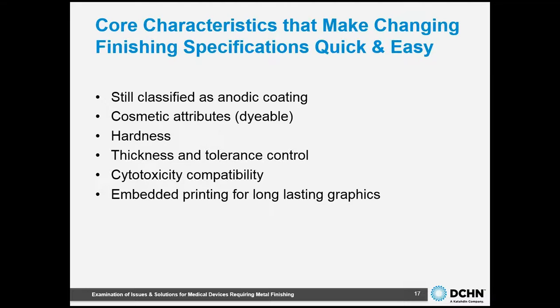So we discussed a lot about best practices solutions to this nagging problem medical device manufacturers will face, but you may be thinking to yourself that specifying this coating is a lot of change and a lot of headaches for you. The reality is, it's really not. Why, you ask? Well, MICRALOX is classified as an anodic coating. It maintains all the positive benefits of Type 2 and Type 3 coatings, like dyeability for cosmetics, hardness for wear resistance, coating thickness for control of dimensions and tolerances, and as stated, it passes RoHS and cytotoxicity tests. And now, because of the hard porous film created by specialized Sanford process power supplies, there is a Sanford print with nearly indestructible markings.